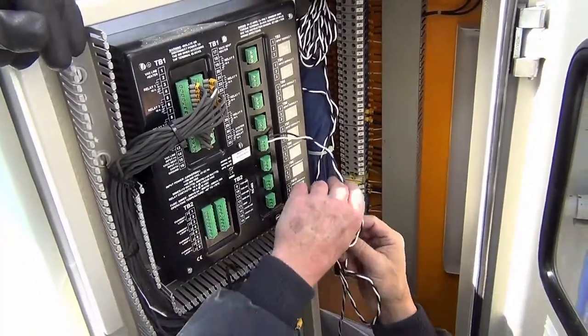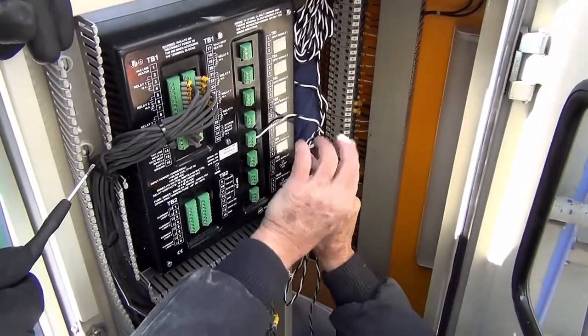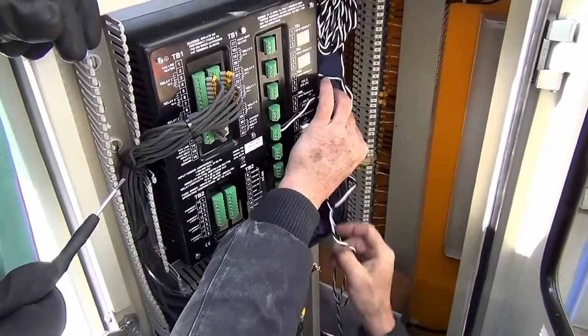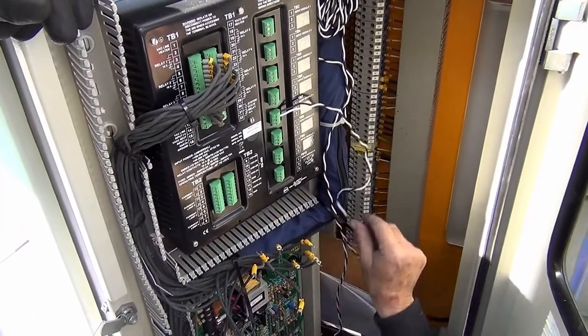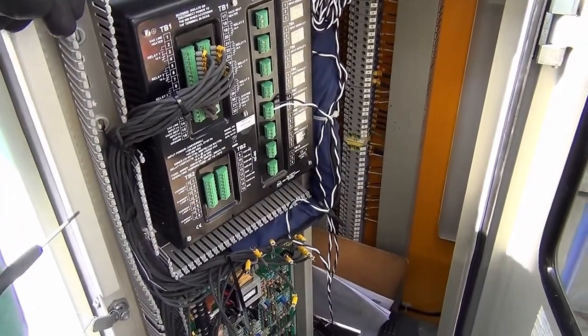With the secondary clamp on CT, you don't have to worry about the polarity. You can wire up the black and white wires to either of the terminals. For more information, you can refer to our ITM 509 manual.